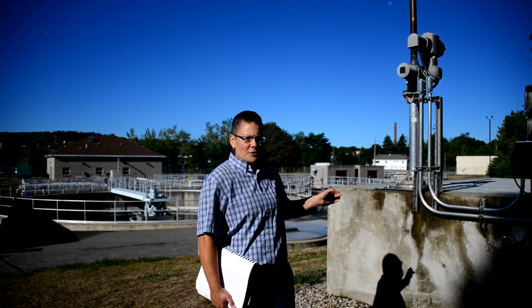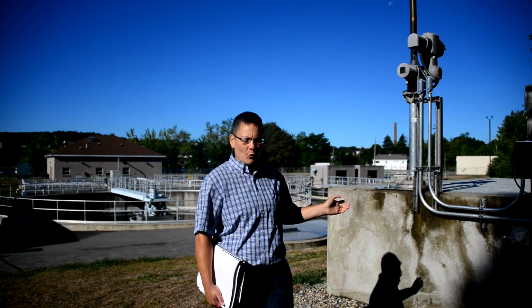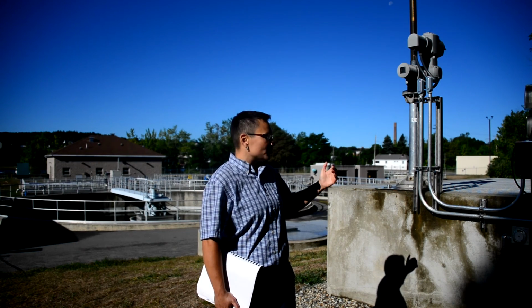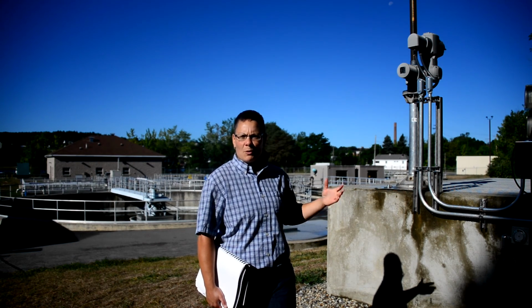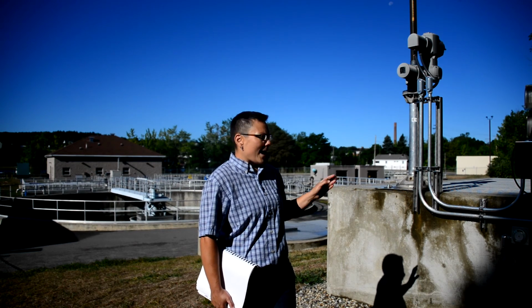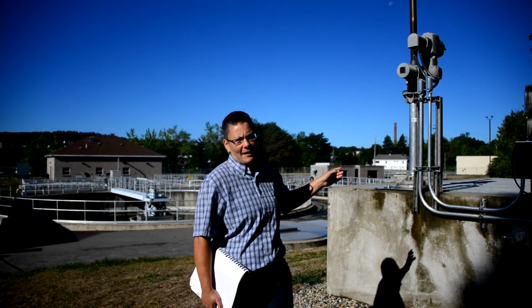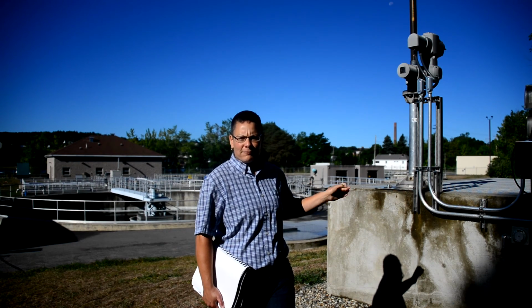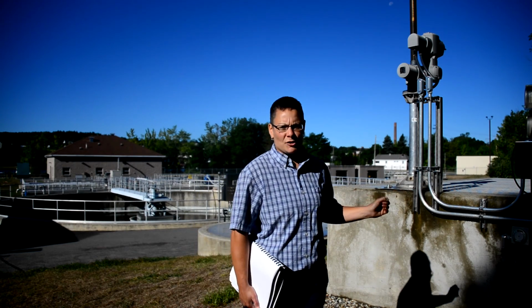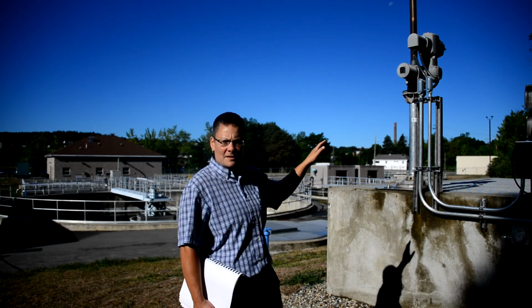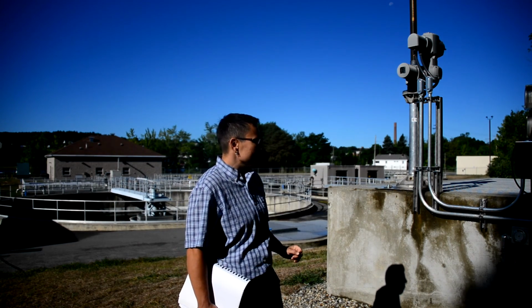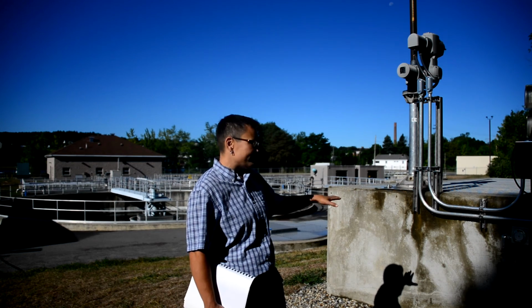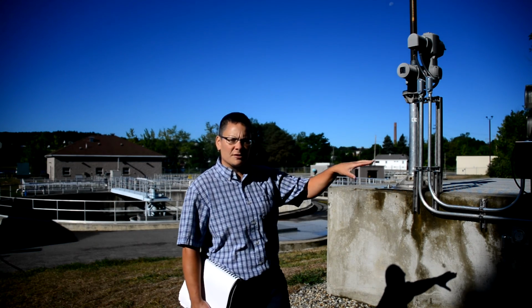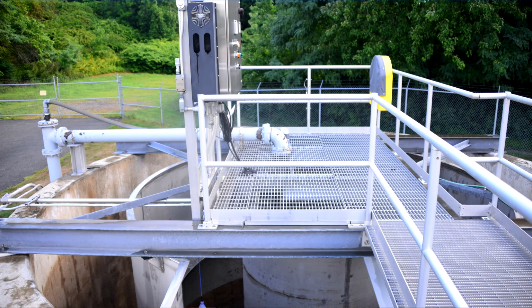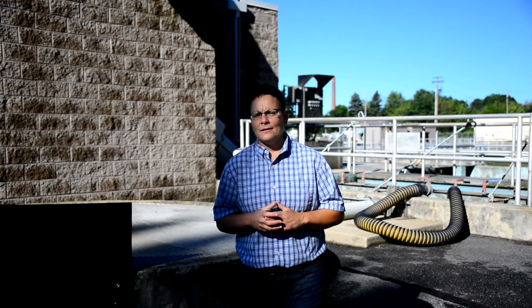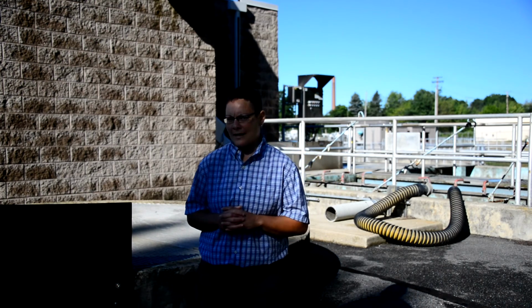This is our diversion structure, or what we like to call here the grassy knoll. This is the influent coming from the west side of the city, which is mostly combined sewer. What happens here is that there's an automated gate valve. When our influent flow hits approximately 8.5 MGD, this gate valve receives a signal to start to close. And what then happens is the level starts to rise until it's high enough to start diverting to our Storm King for stormwater treatment. The east side of the city comes into the plant via 2 10-inch lines.